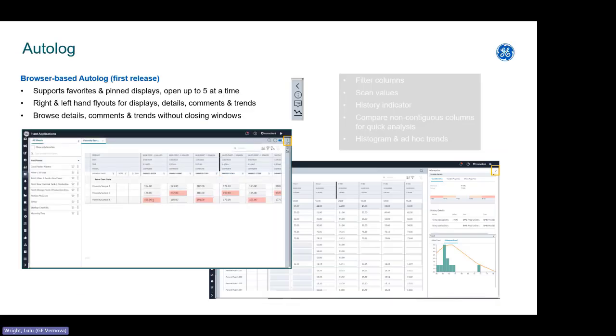These variables can be shown in a couple of different ways. One is what we call autolog, which has a very similar look and feel to the old thick client. You have columns that are time-stamped — for example, if you run a test every 30 minutes, every 30 minutes you get a new column where values come in automatically, manually, or a combination of both. You can see information regarding the event and the variables associated with that event. Clicking any of these values provides additional information and graphs.